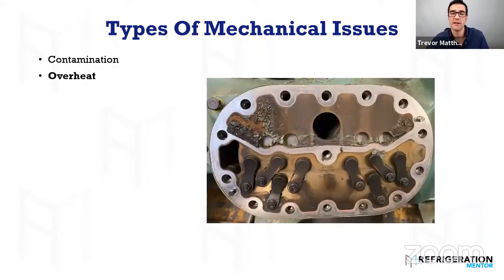Next, overheating. Overheating is one of the leading causes, and we're going to dive in. All the bold ones we'll dive into a little bit deeper. The ones that aren't bold, I'm just going to talk about right now. But as you can see here, this valve plate is black, and anytime you can't rub the blackness off, that means it's major overheat. Major overheat due to many different things, and we'll dive into that in a second. But that is running real high superheat. That's running high compression ratio, and we'll talk about that in a few minutes.